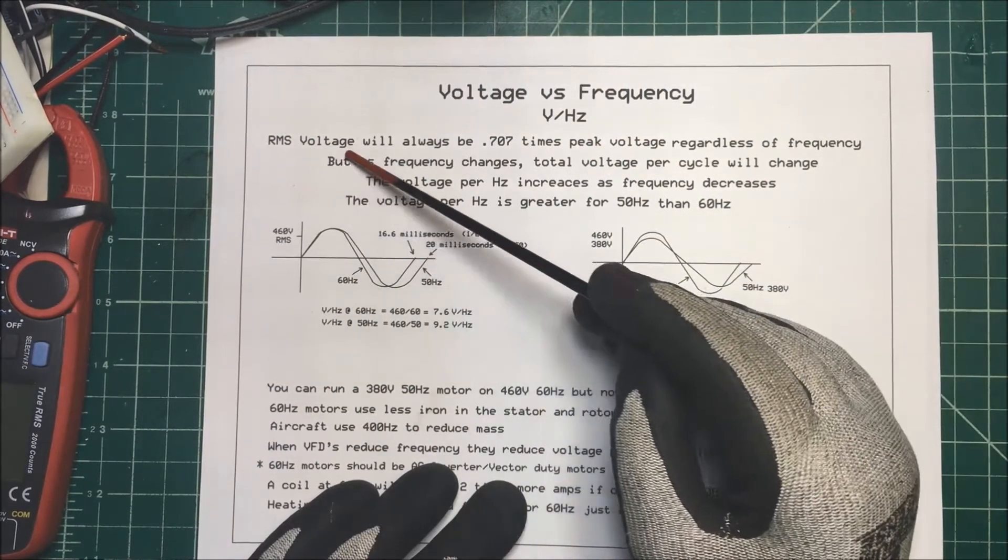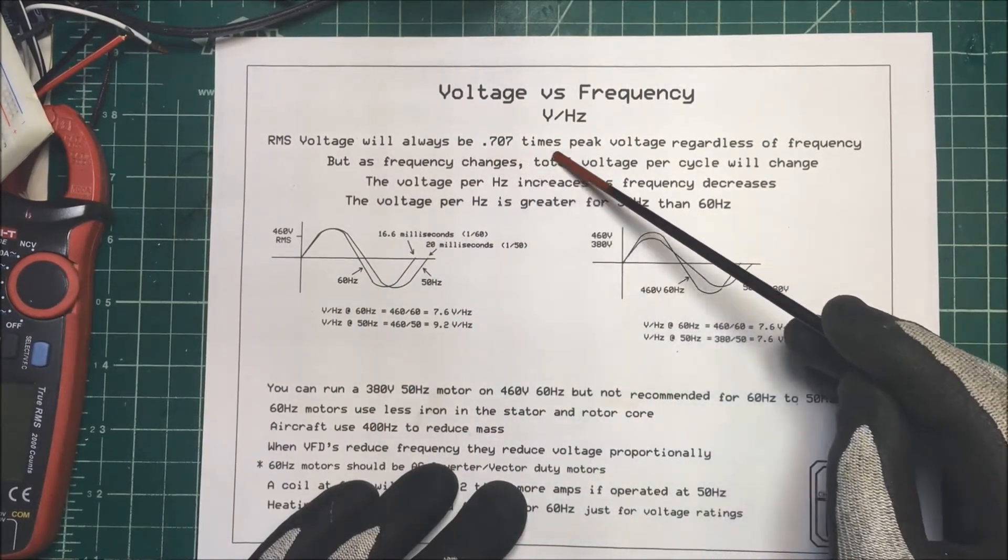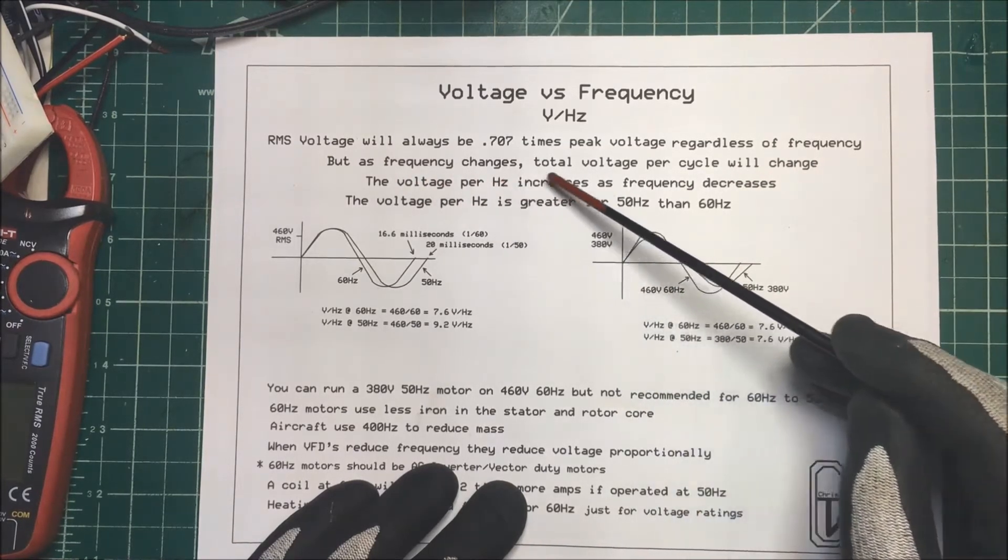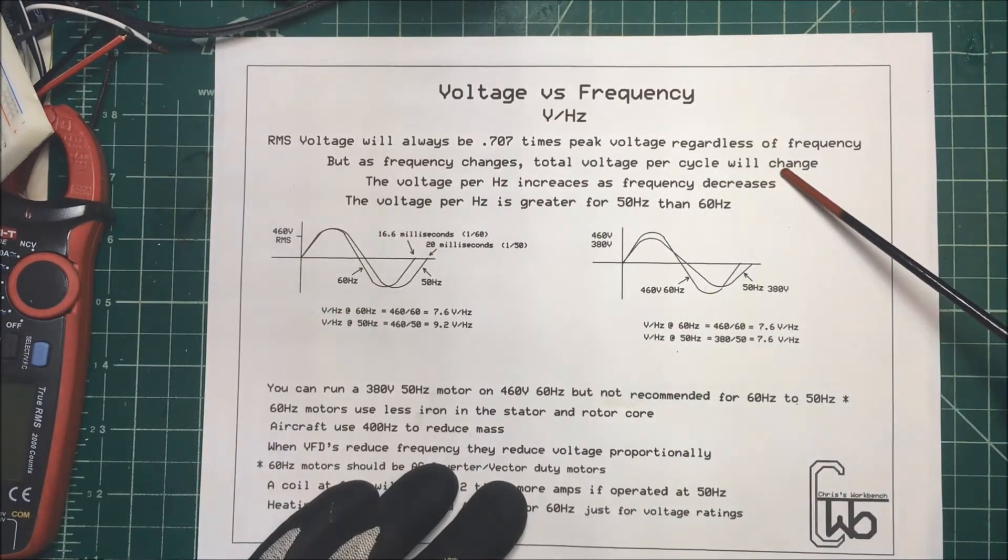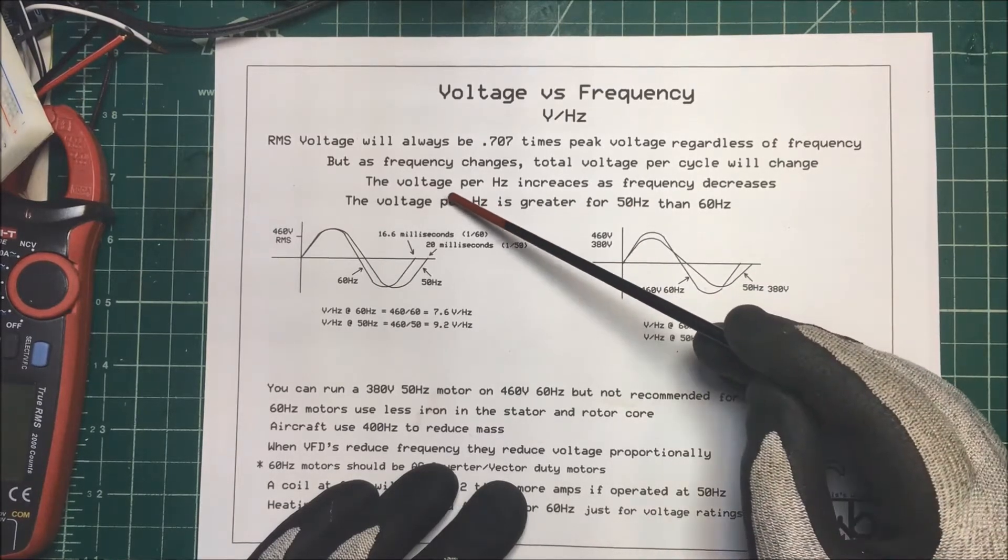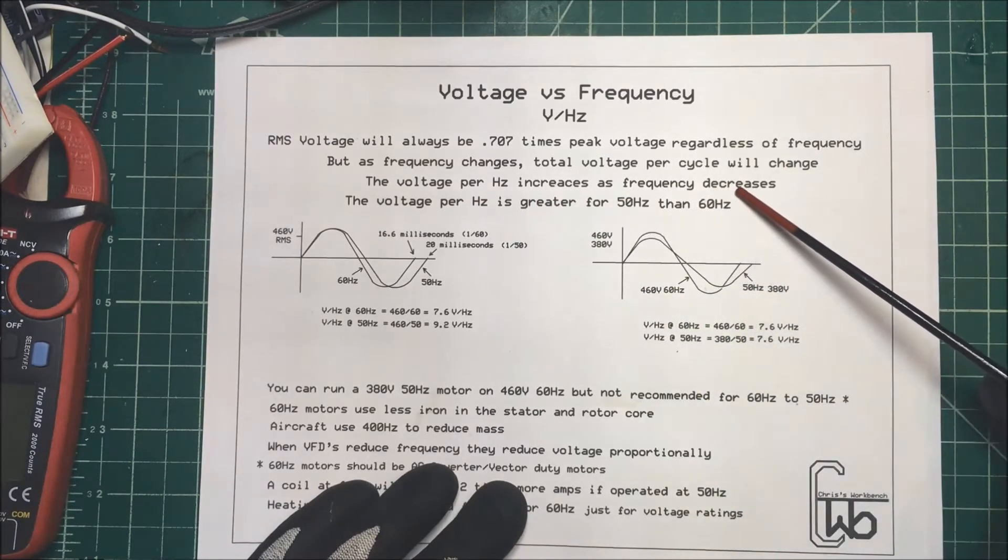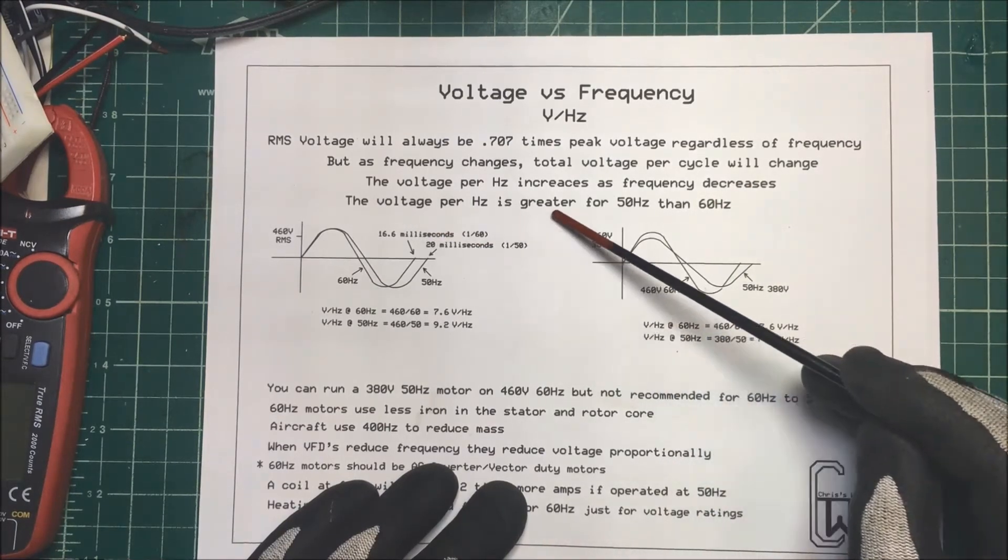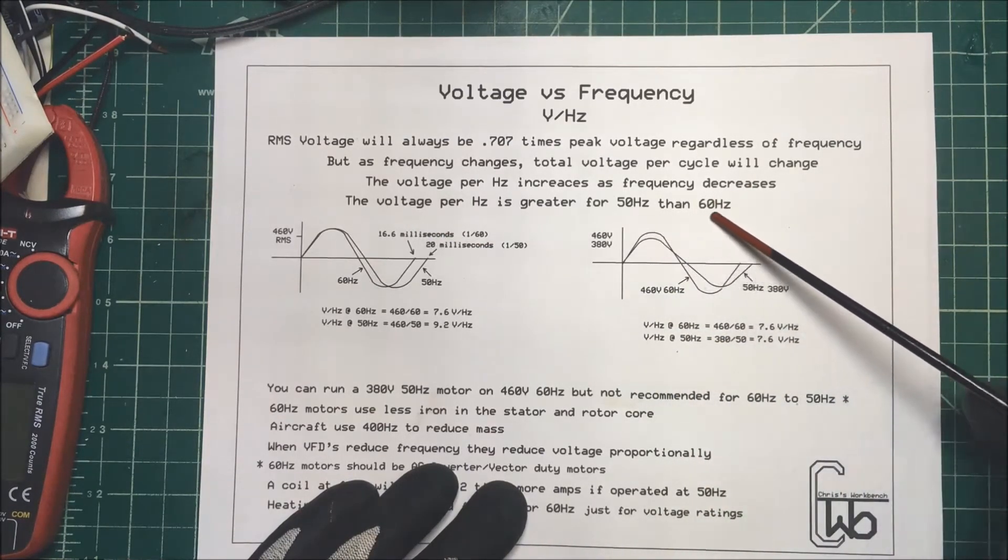Let's talk about voltage and frequency and volt hertz here. Now your RMS voltage will always be 0.707 times the peak voltage regardless of frequency. But as the frequency changes, the total voltage per cycle will change. The voltage per cycle increases as the frequency decreases, and the voltage per hertz is greater for 50 hertz than it is for 60 hertz.